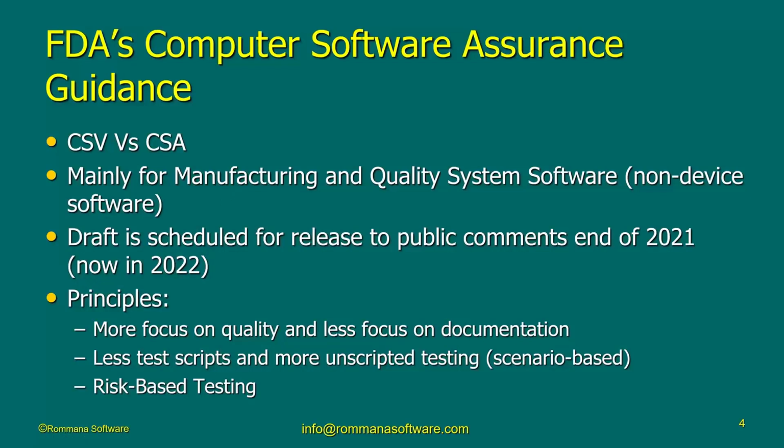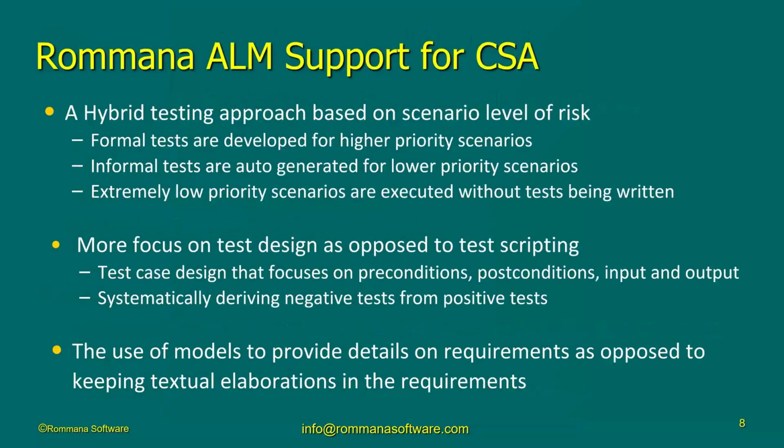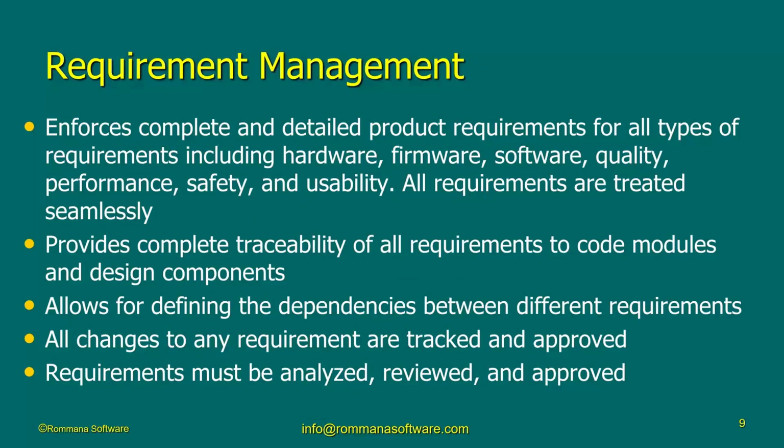We have to be careful here. FDA is not relaxing the requirements that ISO or IEC or any other standards is enforcing. FDA itself has standards that have to do with the medical devices that have high impact on the patient, and those did not change. So what they suggested is that the things that do not have impact on the patient are the systems that are going to go under CSA as opposed to CSV. All right. So as a result, we still have the device software that requires things that are very rigorous.